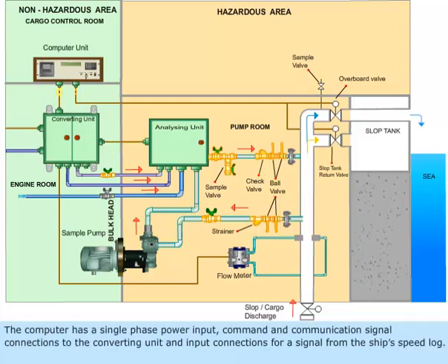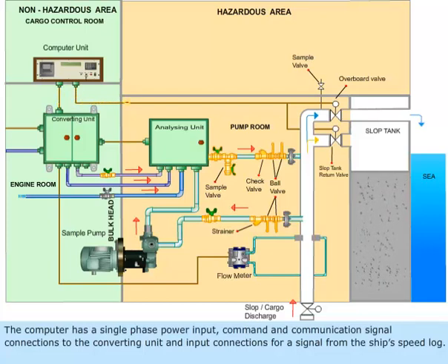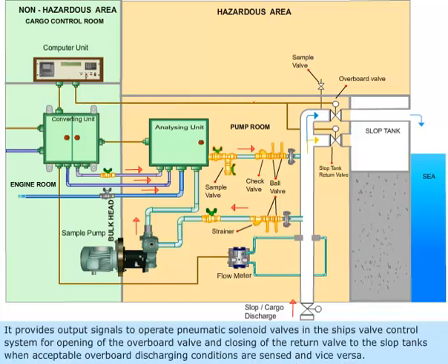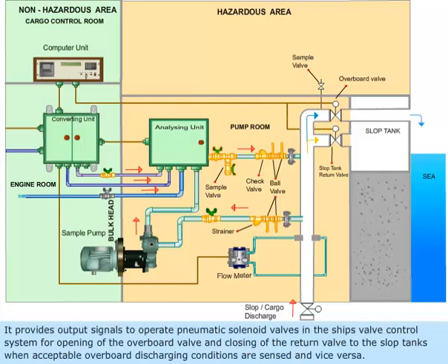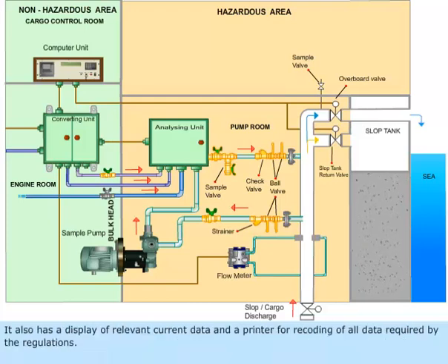The computer has a single phase power input, command and communication signal connections to the converting unit, and input connections for a signal from the ship's speed log. It provides output signals to operate pneumatic solenoid valves in the ship valve control system for opening the overboard valve and closing of the return valve to slop tanks when acceptable overboard discharging conditions are sensed, and vice versa. It also has a display of relevant current data and a printer for recording all data required by the regulations.